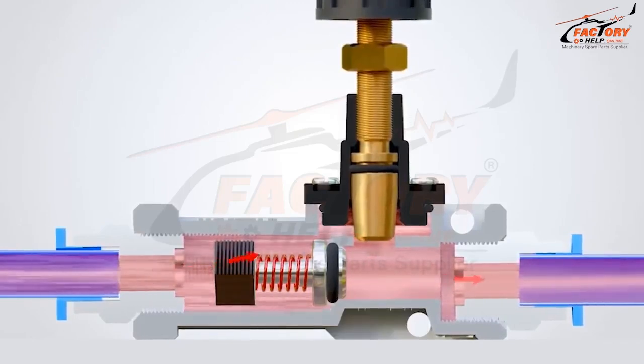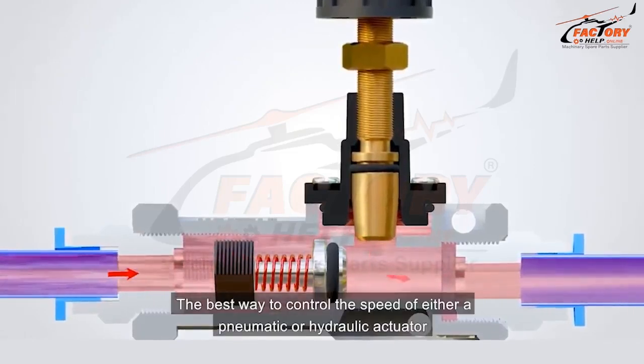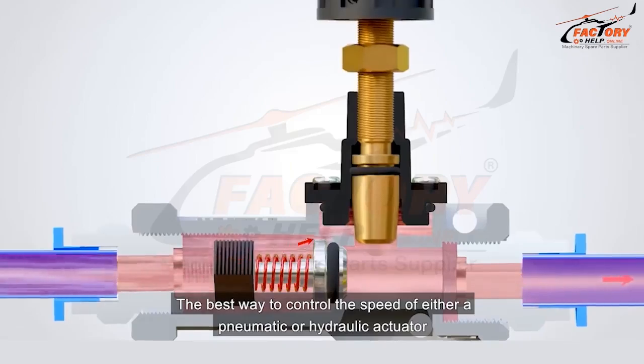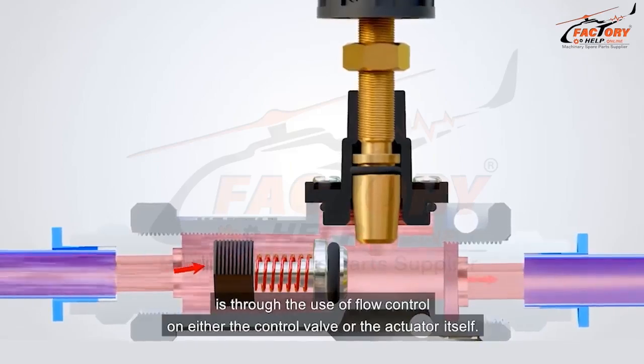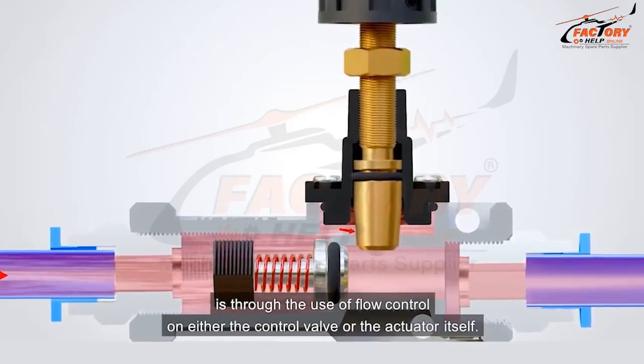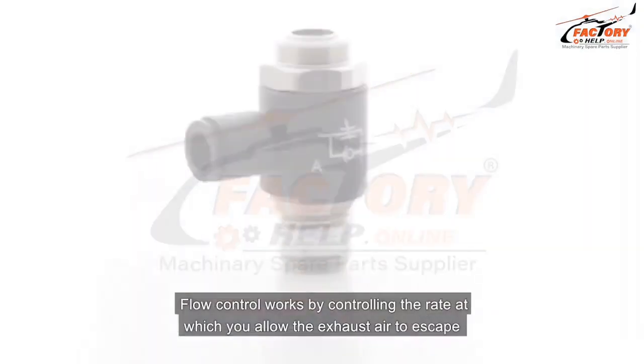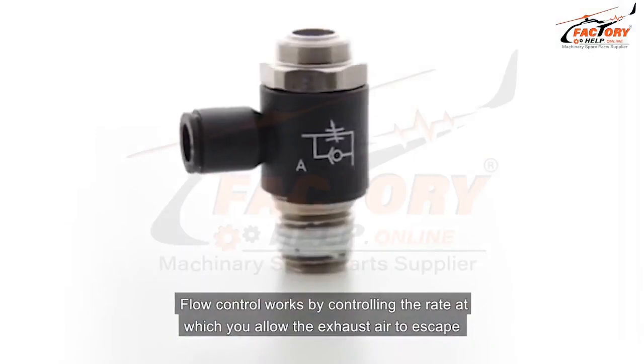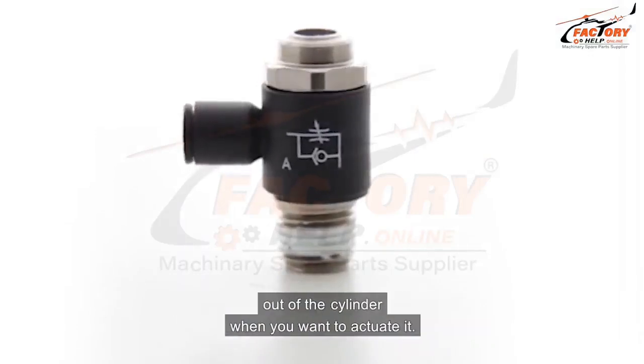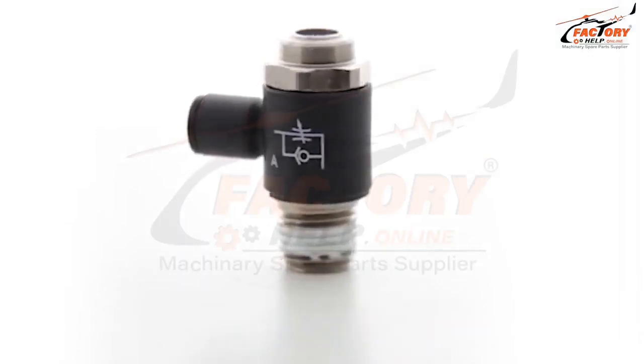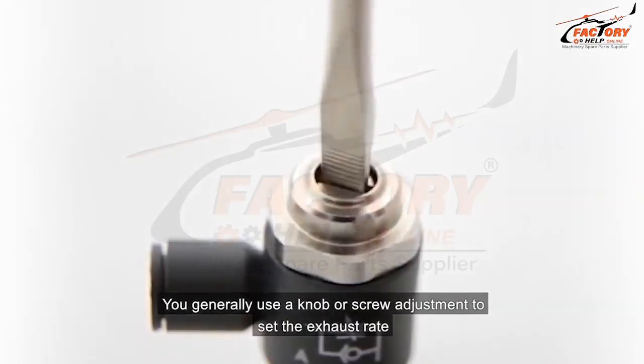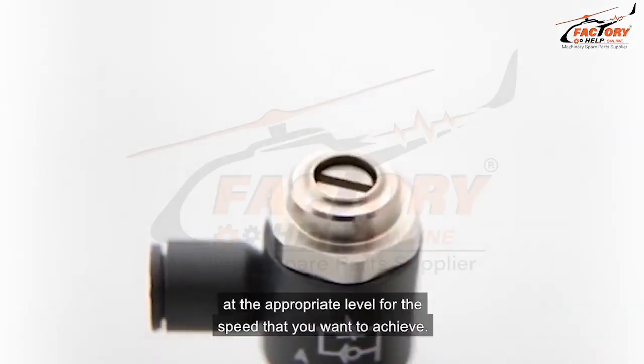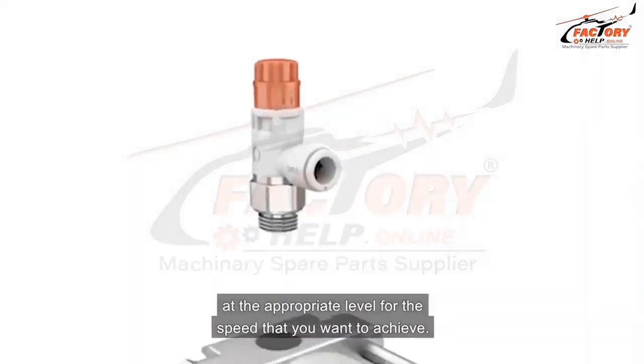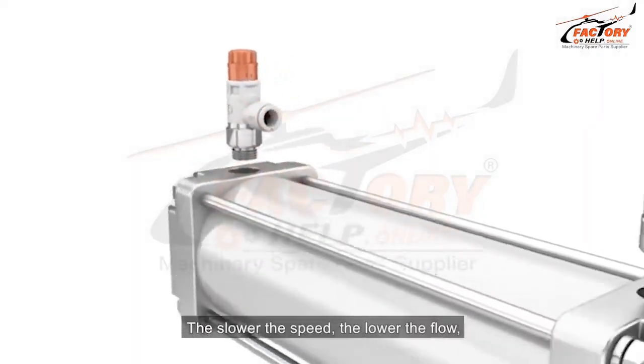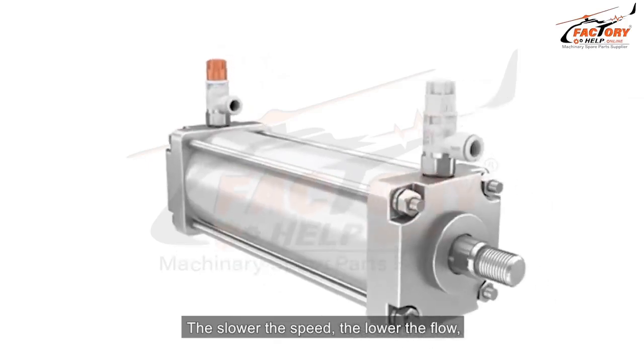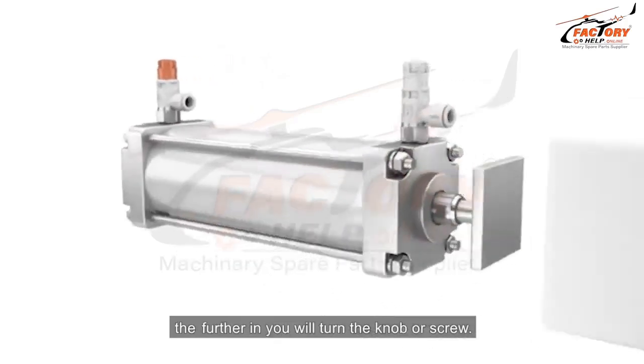The best way to control the speed of either a pneumatic or hydraulic actuator is through the use of flow control on either the control valve or the actuator itself. Flow control works by controlling the rate at which you allow the exhaust air to escape out of the cylinder when you want to actuate it. You generally use a knob or screw adjustment to set the exhaust rate at the appropriate level for the speed that you want to achieve. The slower the speed, the lower the flow, the further in you will turn the knob or screw.